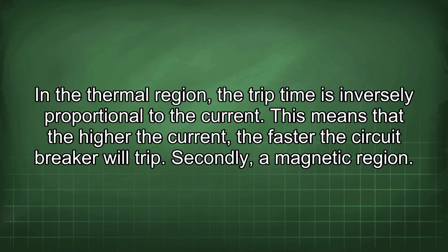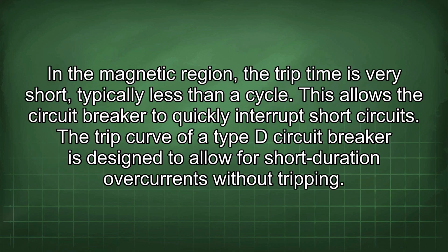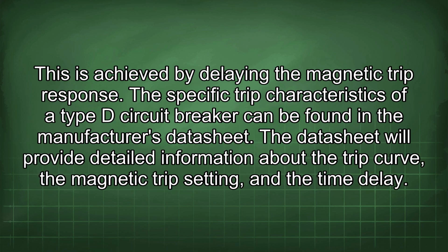Secondly, a magnetic region. In the magnetic region, the trip time is very short, typically less than a cycle. This allows the circuit breaker to quickly interrupt short circuits. The trip curve of a Type D circuit breaker is designed to allow for short duration overcurrents without tripping. This is achieved by delaying the magnetic trip response. The specific trip characteristics of a Type D circuit breaker can be found in the manufacturer's datasheet. The datasheet will provide detailed information about the trip curve, the magnetic trip setting, and the time delay.